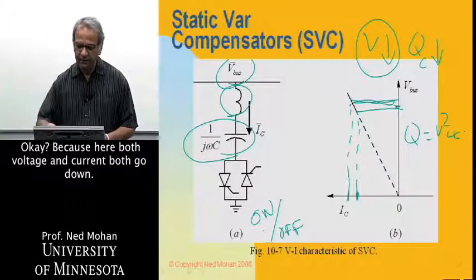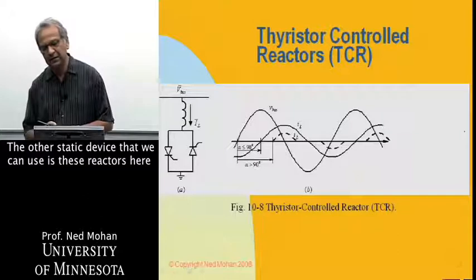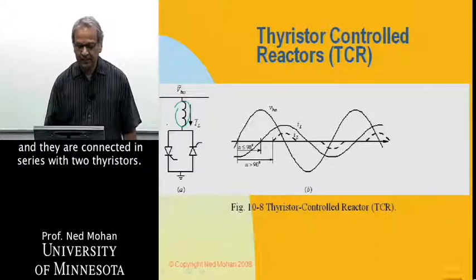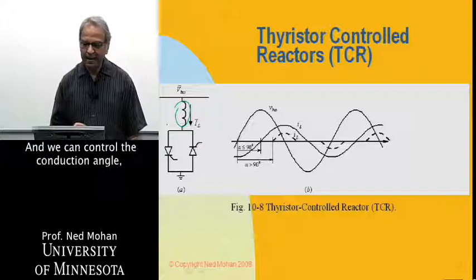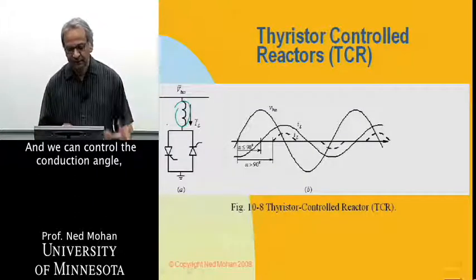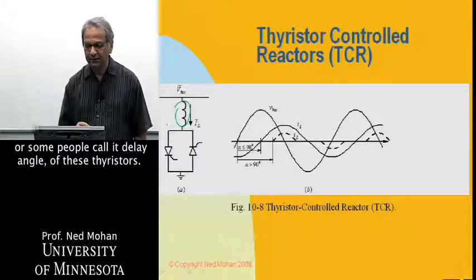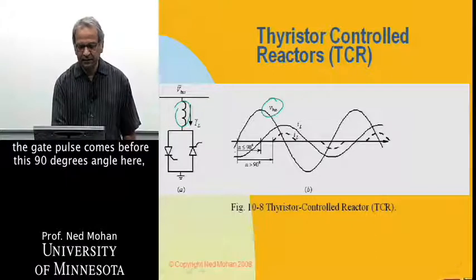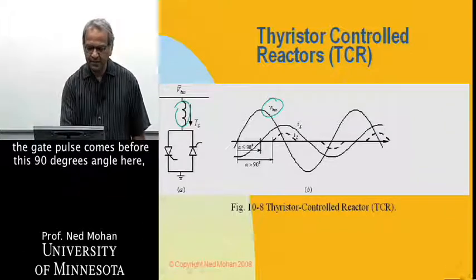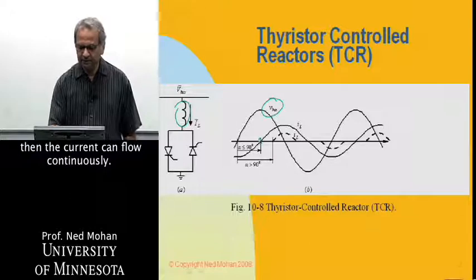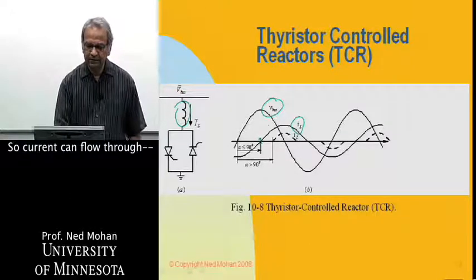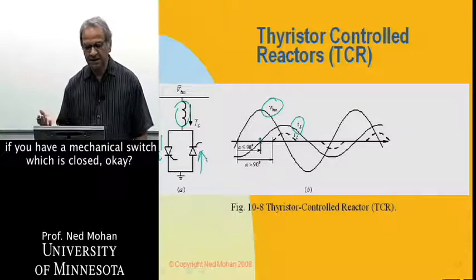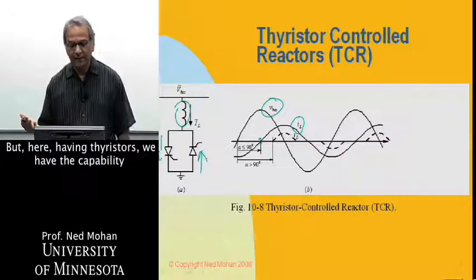Because with a capacitor, both voltage and current go down together. The other static device we can use is a reactor connected in series with two thyristors, where we can control the conduction angle, or delay angle, of these thyristors. If the gate pulse comes before the 90-degree angle with respect to the bus voltage, the current can flow continuously — in the positive direction through one thyristor and in the negative direction through the other, as if you have a closed mechanical switch.